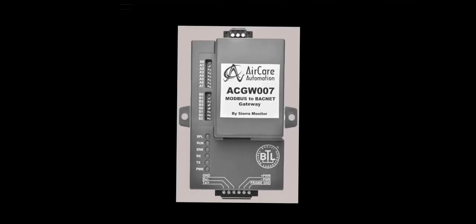The universal control card for ECM units communicates with the building management system using the Modbus RTU protocol. However, if the building management system is not a Modbus network, gateways which translate between Modbus RTU and other communication protocols such as BACnet IP, BACnet MSTP, and LonWorks are available.